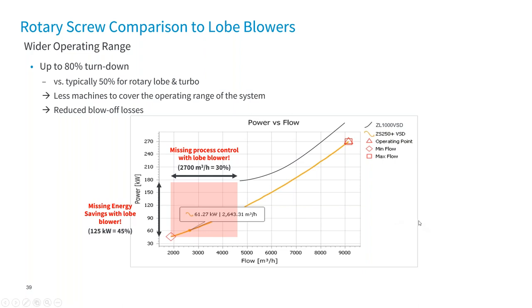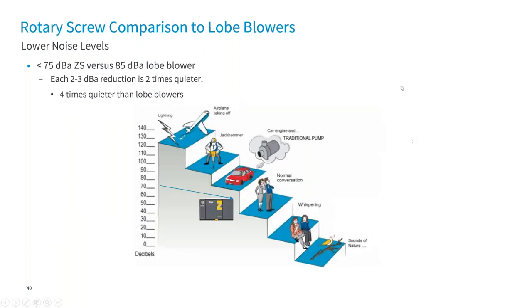The screw is a generally low capital cost machine — more than the lobe, but less than the centrifugals. It's got that wide turndown range and a high package efficiency across the whole range. The noise level on the screw is typically about 10 to 15 decibels lower than the rotary lobe, and about 5 to 10 decibels higher than the high-speed turbo. When comparing screw to lobe: lower noise, wider turndown, more efficiency for a similar cost. But in general, the rotary lobe blower is always going to be your lowest cost option.